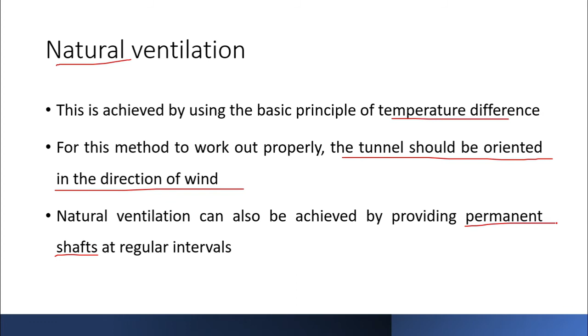Just remember that if your tunnel orientation matches the direction of the wind, then you can go for a natural system. It's not that you want to install a natural system and purposefully change the orientation of the tunnel. The decision of which direction to orient the tunnel depends on other factors, such as the type of obstruction and your connecting road, not on what type of ventilation you have to provide. But it's an added benefit if your tunnel is oriented in the direction of the predominant wind, then you can go for natural ventilation. And for natural ventilation, having shafts at regular intervals will also be a very added benefit.